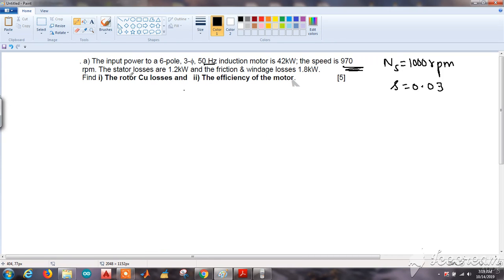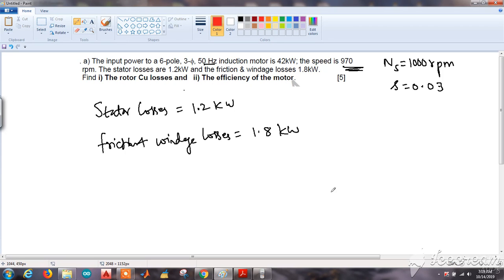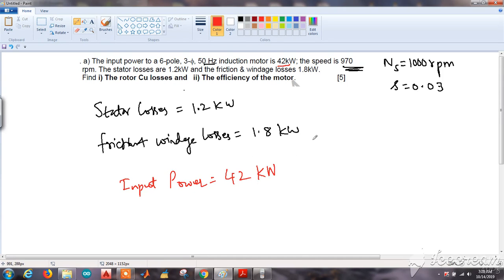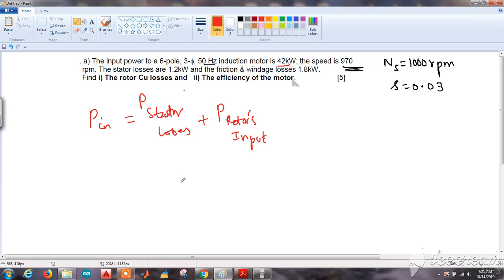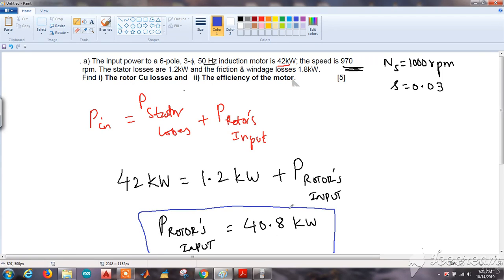The stator losses and friction and windage losses are given, and the input power is also given as 42 kW. Since input power equals stator losses plus rotor input, we can find the rotor input. Substituting the known values, the input power to the rotor comes out to be 40.8 kW.